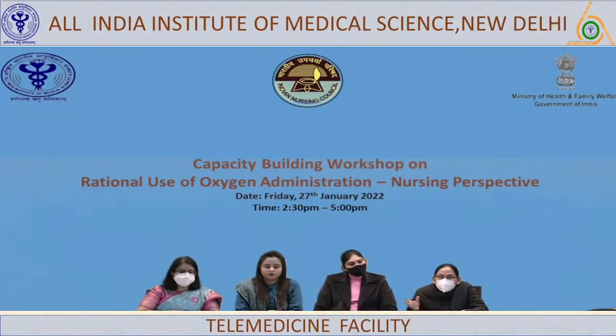Coming to the water reservoir, where we put the sterile water, it has to be cleaned every 24 hours. There is a small tube behind the nebulizer. From that tube, we drain the water and clean that area. The tube can also be cleaned with a brush to remove debris, and that is how we clean the nebulizer. And the spacers.